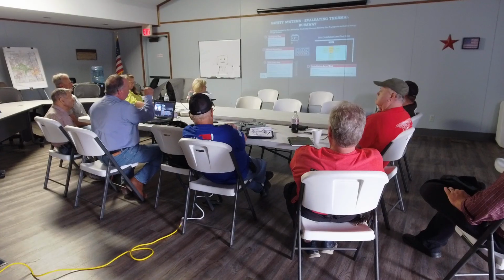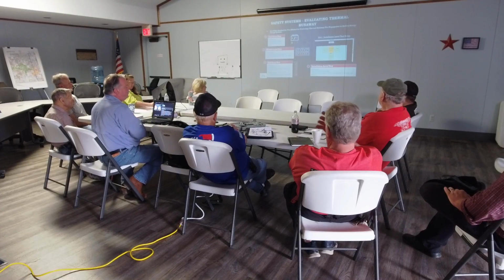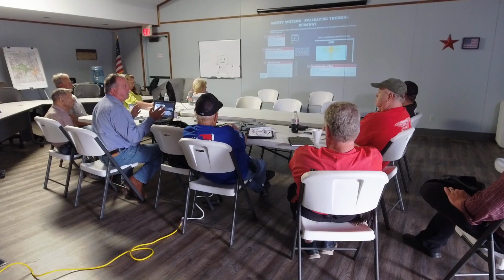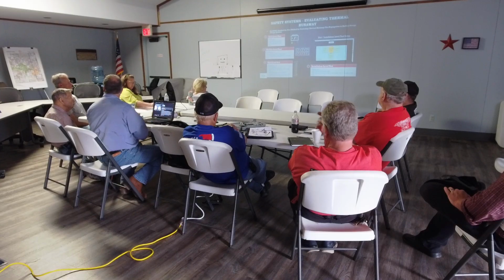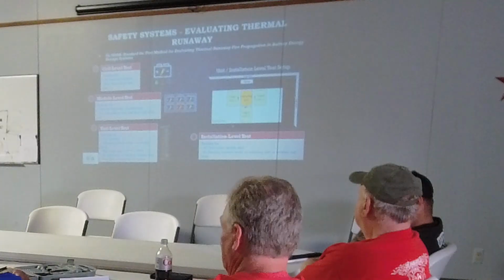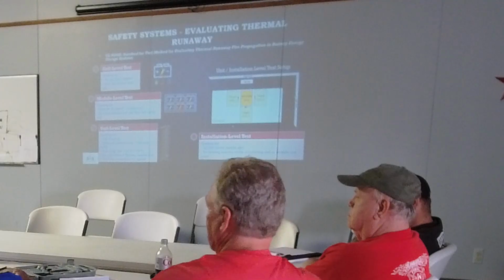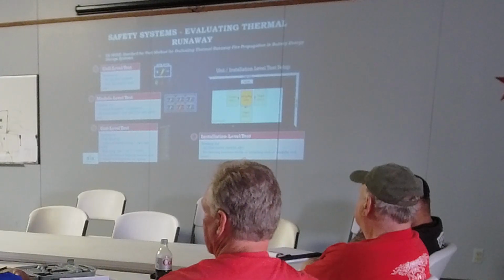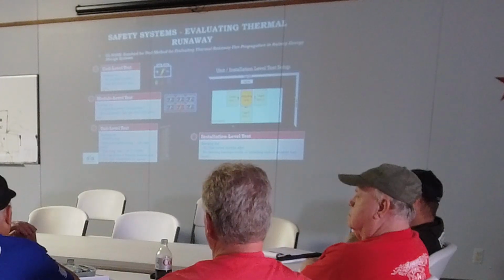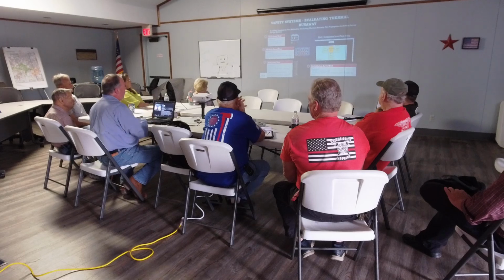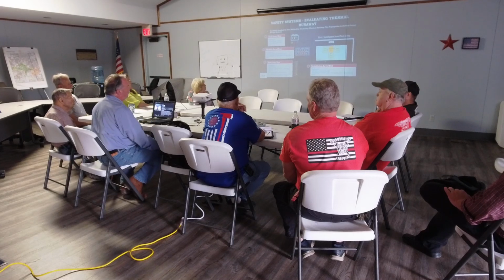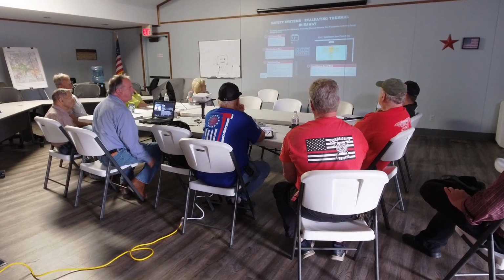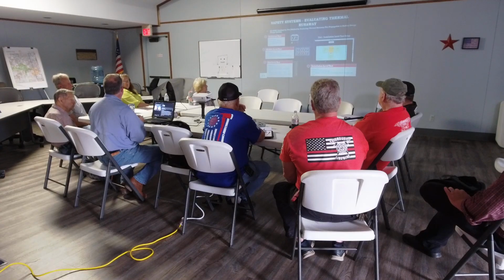On that unit level test, we're not allowed to use any mitigating factors. We can't use our BMS, the battery management system. We can't use ventilation. We can't do anything. It's the worst case scenario. If they get through that test and it hasn't run away and done anything bad, then they can go ahead and do what's called an installation level test, where we can actually use all of our controls and try to stop the event before it happens.